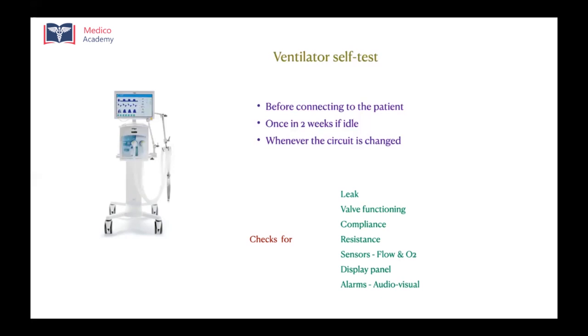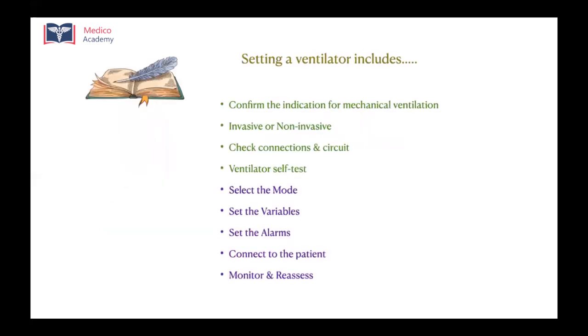And it also checks whether the alarms, even the audio alarms or the visual alarms or the audiovisual alarms, are they working fine? Whether the high priority, medium priority, and low priority alarms are working fine will be checked. So that's about ventilator self-test. So we have checked the connections and circuits and done a ventilator self-test as well. So your next is to select the mode. We select the mode, variables, and alarms before connecting to the patient.